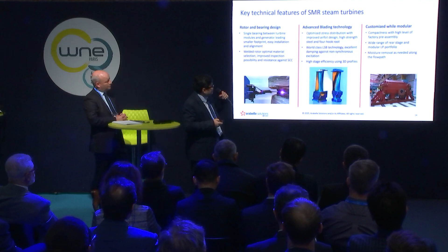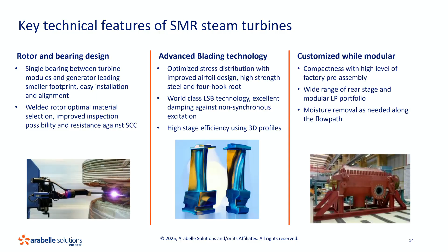The last element is modularization and standardization, which is quite important for SMRs, and we kept that concept. The HP turbine goes to site fully assembled and just needs to be aligned. The LP goes in a minimum number of parts, two or three as required, and can be assembled and aligned on site.